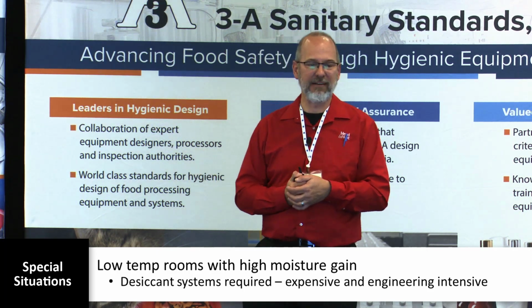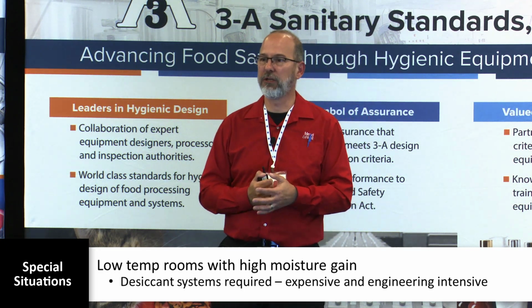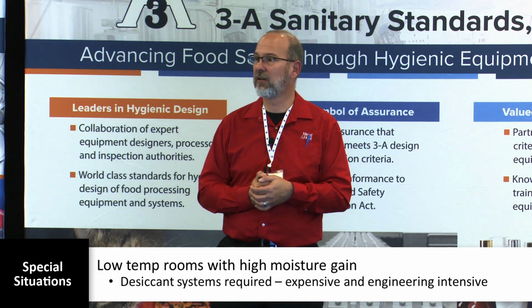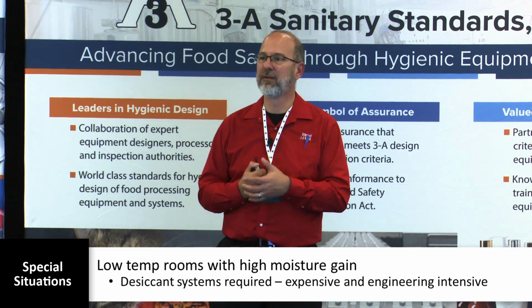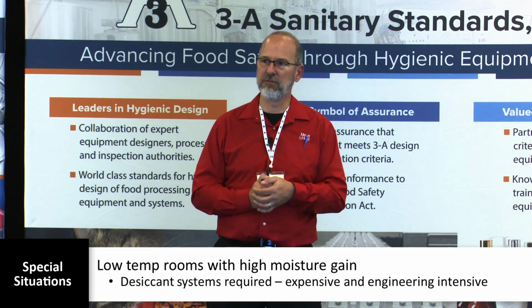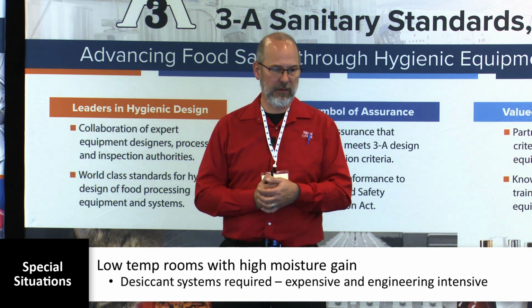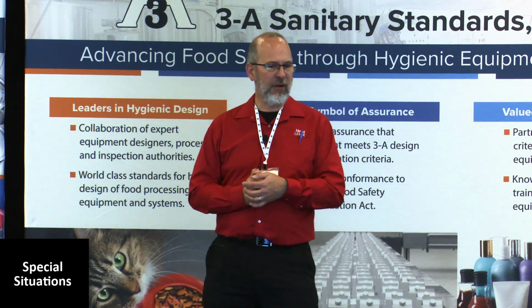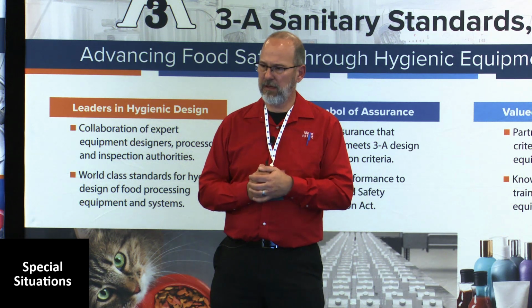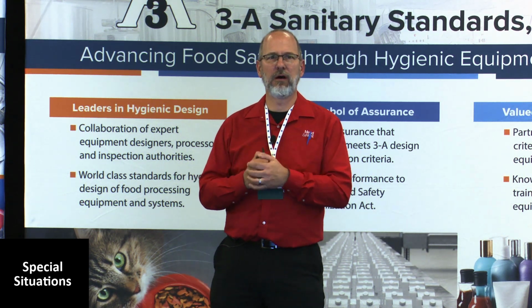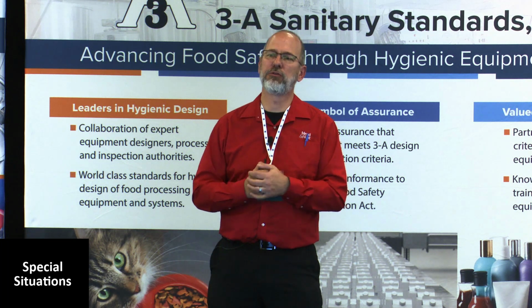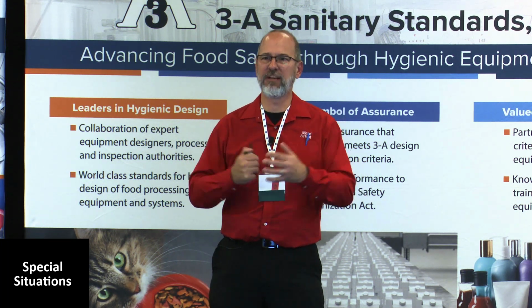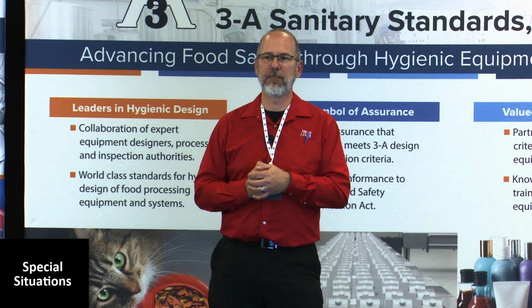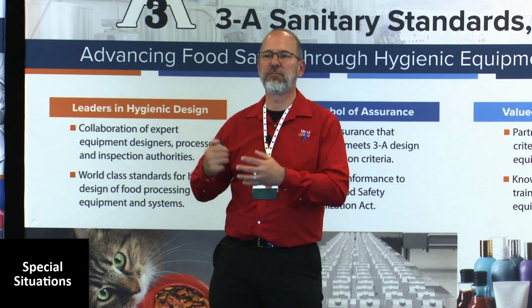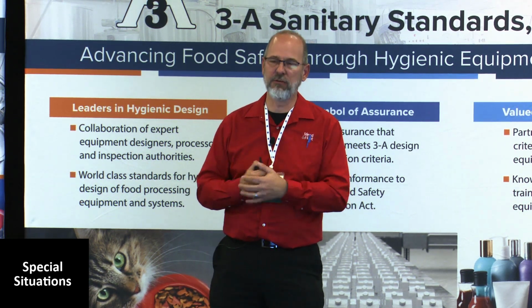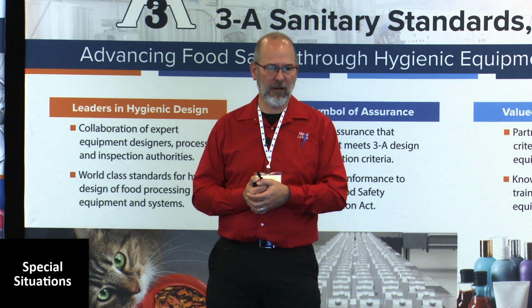So, but that really is the best solution if you've got really cold rooms and high humidity in the rooms, because a normal air handler has a difficult time getting rid of all that moisture when you've got a low temperature space with high humidity. And one other thing I wanted to comment on is I'm kind of seeing a shift away from low temperature process rooms where you've got evaporators hanging in the room to a move to getting rid of the evaporators and putting large penthouses or large air handling units on the roof to replace them.